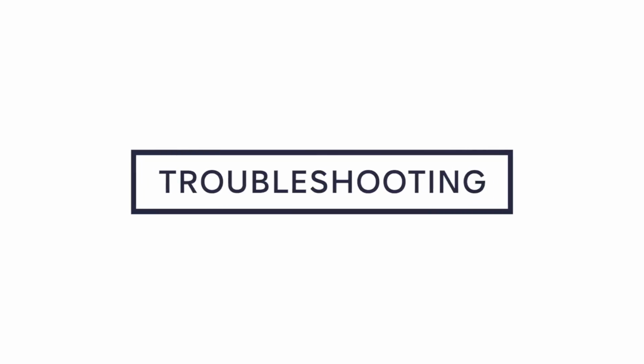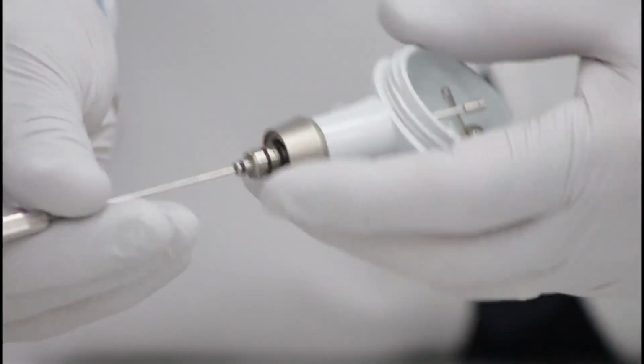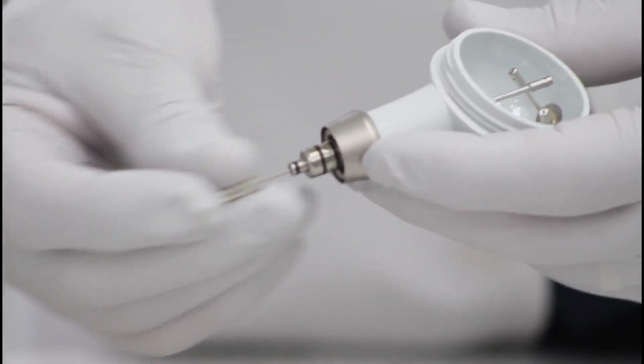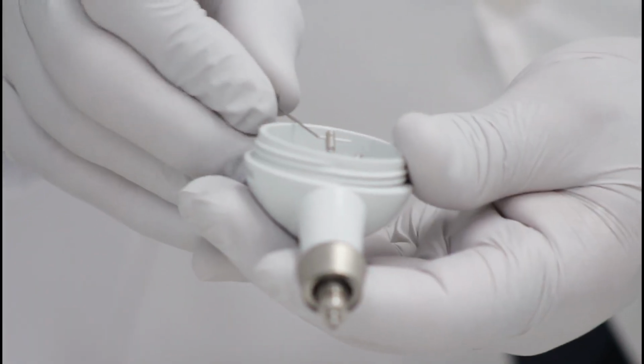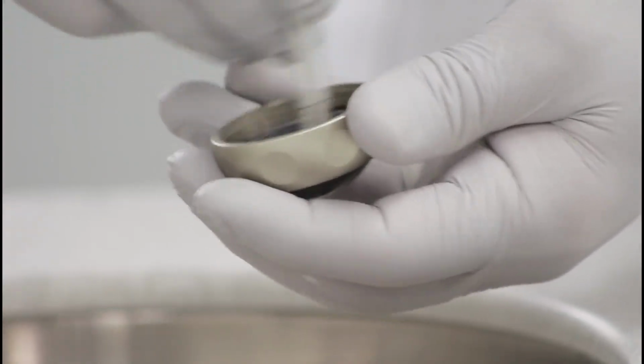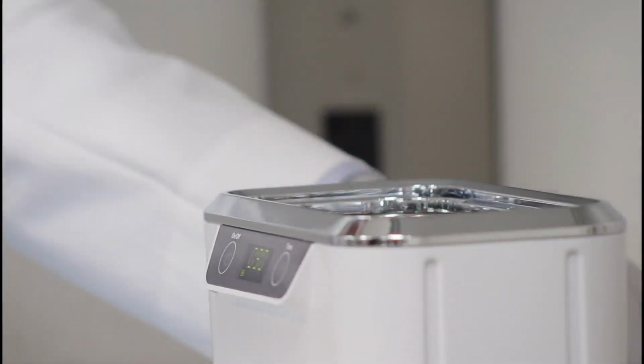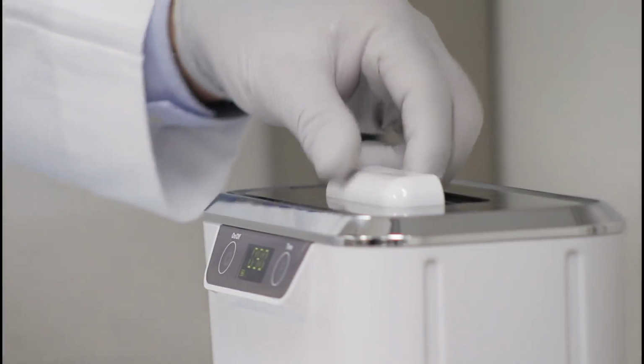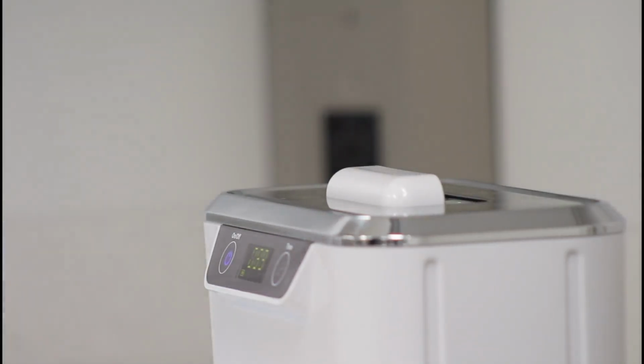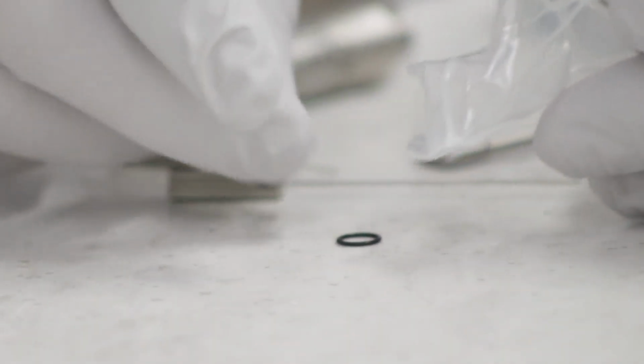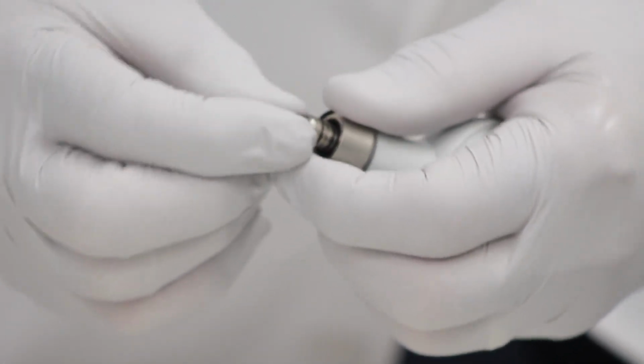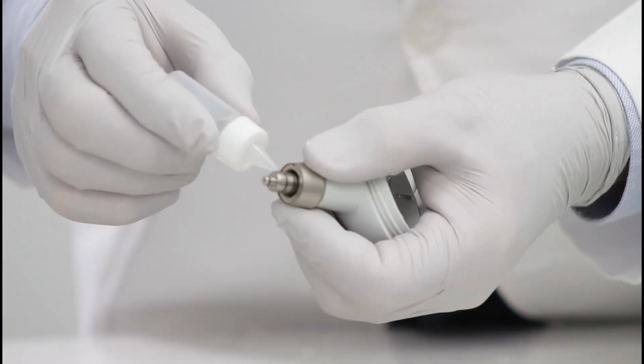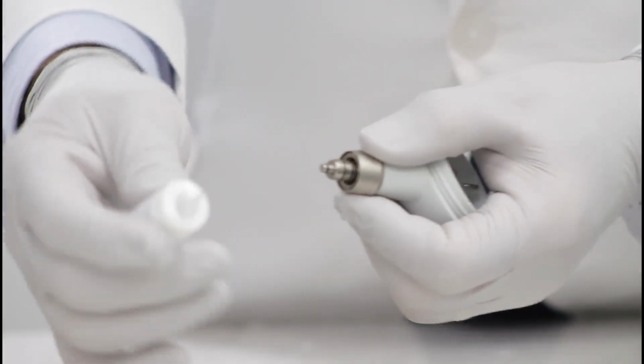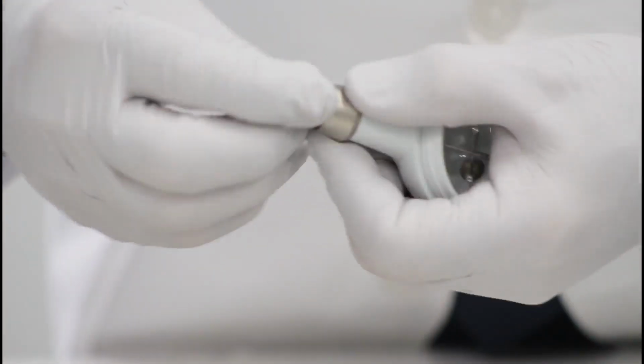Troubleshooting. Powder clogging. Remove the nozzle from the handpiece and clean the inside of the nozzle and the handpiece with the supplied cleaning wires, file, and brush. After removing the solidified powder, perform deep cleaning with ultrasonic bath from earlier in the video. Water leakage. Replace the O-rings at the handpiece joint section after cleaning and drying the grooves. Apply a drop of the little oil container supplied with the kit and rub it in with your fingers.